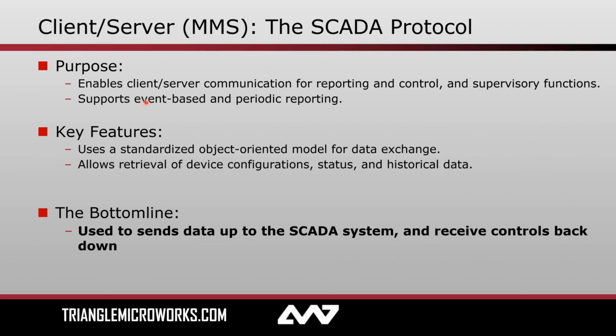From a high level, client server is the SCADA protocol. It's the one that we're going to use to pass data from our IEDs or servers down at the bottom that are interfacing directly with our conducting equipment and performing the protection and automation functionality of our substation. Data from those devices will be aggregated into reports. They also might be read, in either case sent up to a client at a higher level for historizing, to store in some sort of historian database. Also, that's where we have our HMI, where we can see in a graphical way what's actually happening in our substation. And finally, we can issue controls back down from that higher plane, from the clients, maybe to open a particular breaker. Of the three communication protocols we'll be discussing today, this is the one that has the most similarity to other communication protocols outside of 61850 that have been common in the substation space for some time, namely DNP3 and 60870-5-101 and 104, in the sense that they fulfill a similar role.